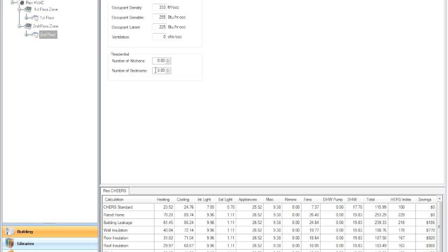That is very important information that you need to specify for EnergyPro if you're going to do multiple rooms or multiple floors in the building, because this tells EnergyPro that you're going to have 3 occupants or 3 bedrooms worth of people upstairs, and downstairs you're going to have all the heat gain associated with the cooking and kitchen appliances. So do be sure to specify that correctly.